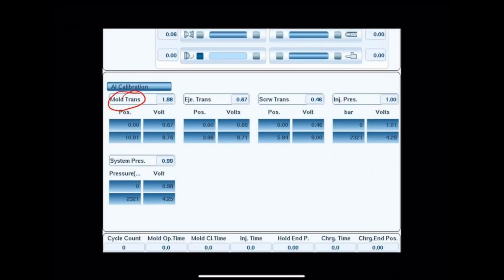So what you do, you put your mold position to 0, which is lock up. Whatever value you get in here, these are voltages. Whatever value you have here, you put it here. So then you move your mold all the way open. And whatever value you get here for voltage, you put in that box. And you do the same thing for all the transducers.